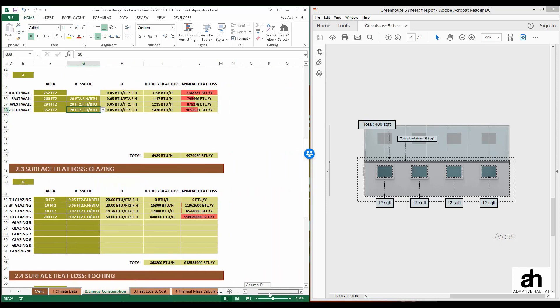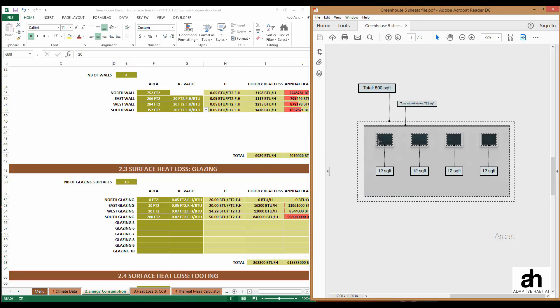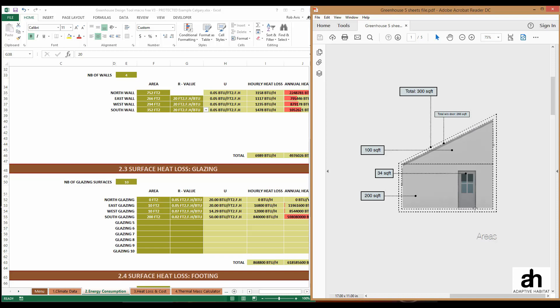In section 2.3, we're going to calculate surface heat loss out of the glazing. The number of glazing surfaces is going to be dictated by the number of different areas within the respective orientation — north, east, west, and south — not including the primary glazing surface on top of the greenhouse. The south facade we're going to classify as one glazing surface. The main glazing area on top we count as one independent glazing surface. The northern wall, west glazing, and east glazing surface — which is going to be the door — we each refer to as one glazing area. So we're going to enter five different glazing areas.